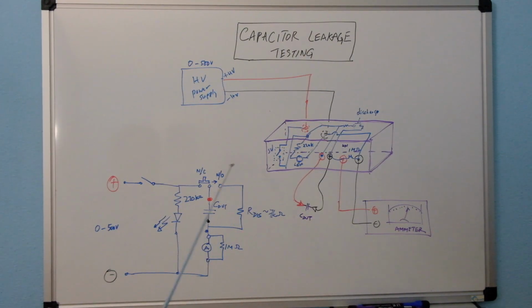So the basic circuit is really here. I have, in this case, a supply that is connected on this side, and this is meant to go up to 500 volts or so. I have a main switch here which, once powered on, powers on this LED through this high value resistor. As soon as this is on, you immediately see there's voltage in the circuit. So you want to be careful that you don't touch anything, especially with the high voltage coming in.